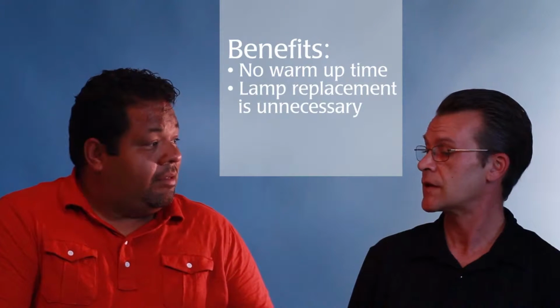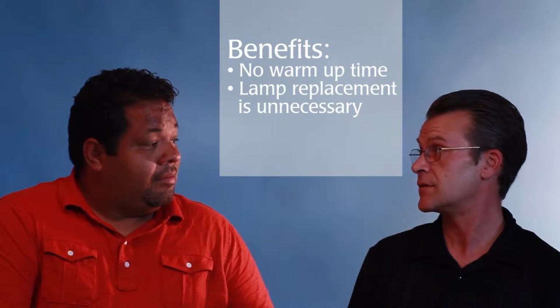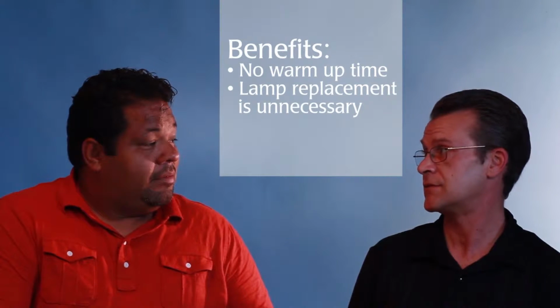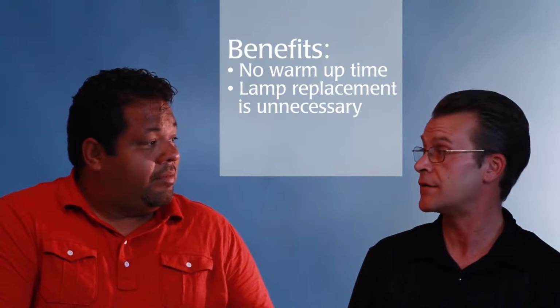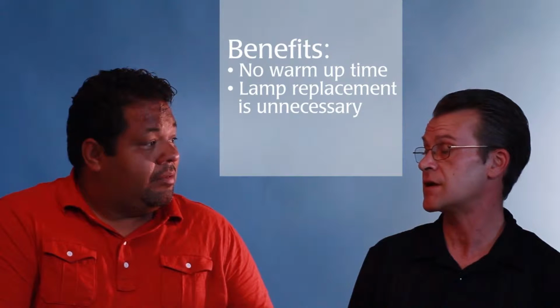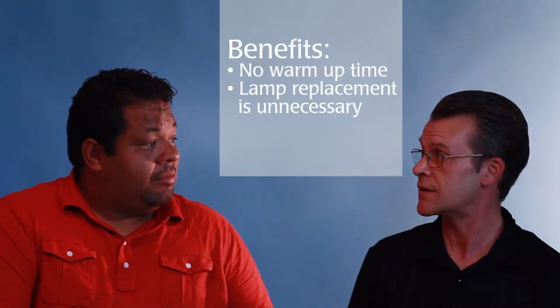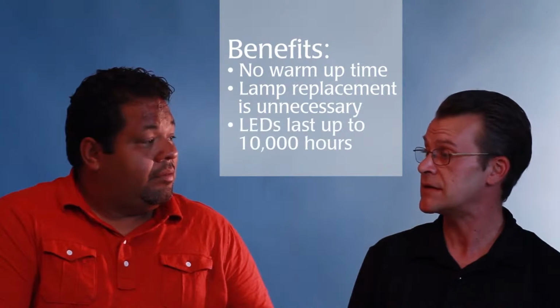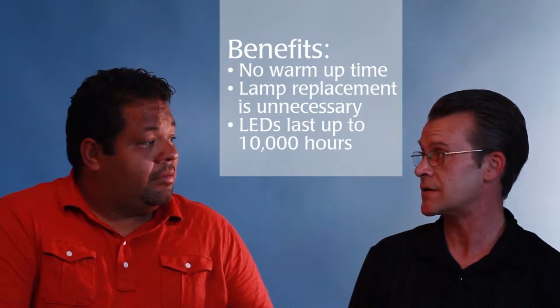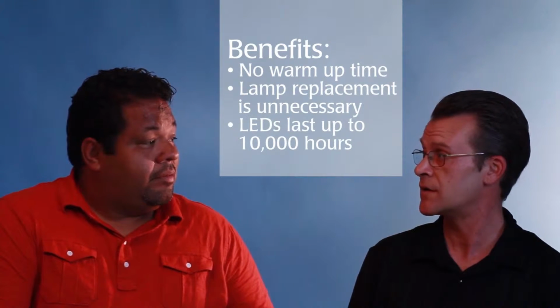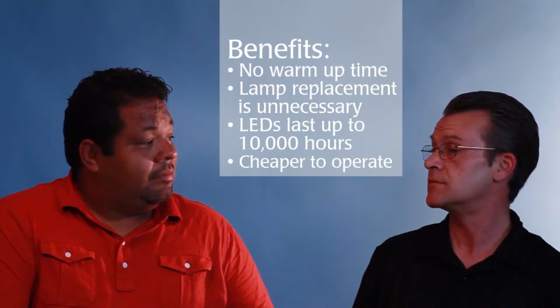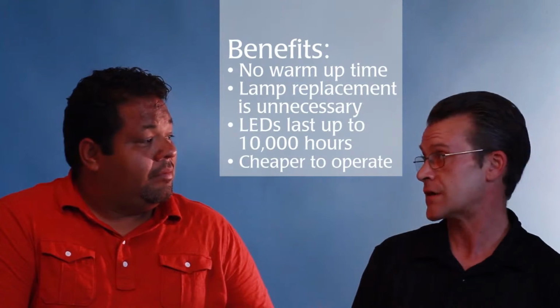That's great. Okay, as a second benefit, you do not have to replace the lamps. If you use either a mercury vapor or a halogen lamp, you have to replace the lamps anywhere between every 1,000 and 2,000 hours. These LEDs actually have a lifetime of over 10,000 hours, which means in the long run, you're going to save a lot of money on the maintenance of the instrument over time. Long-term savings are always good.